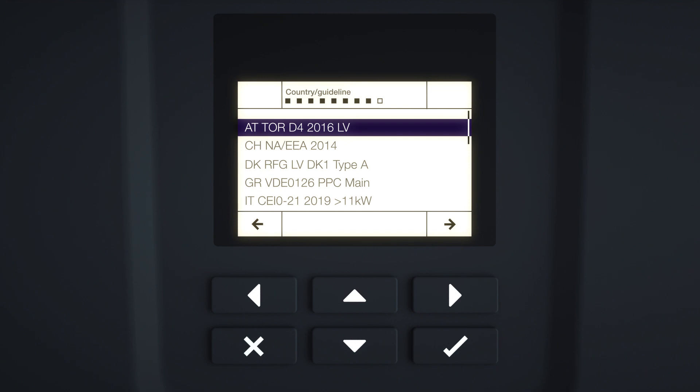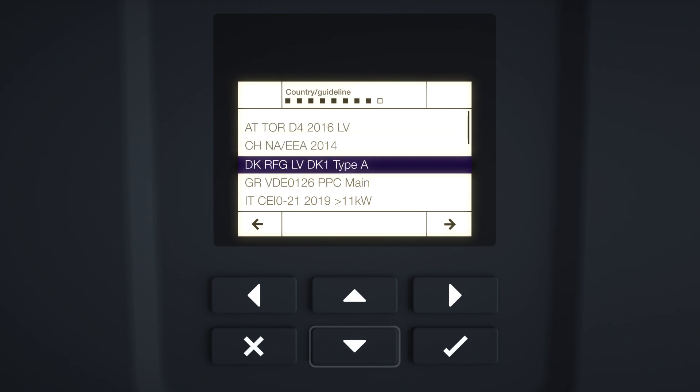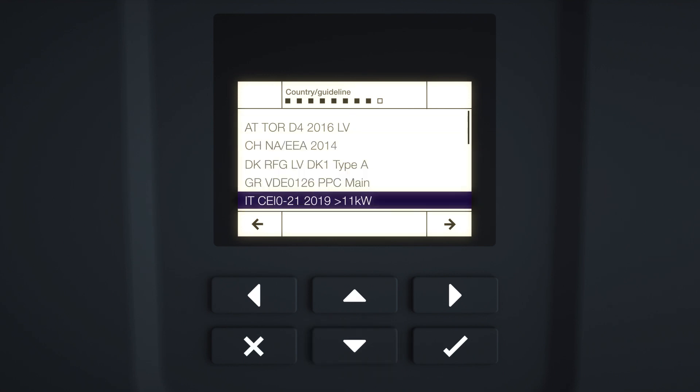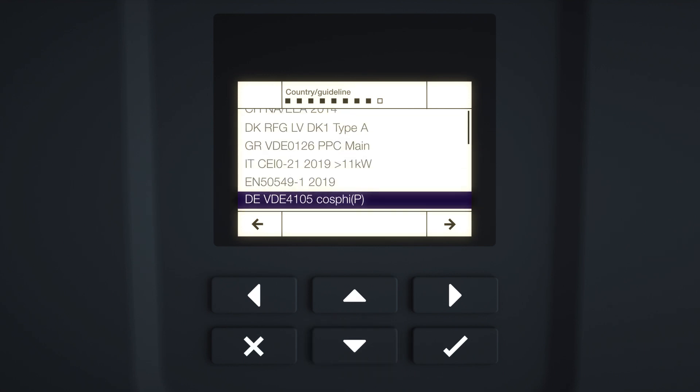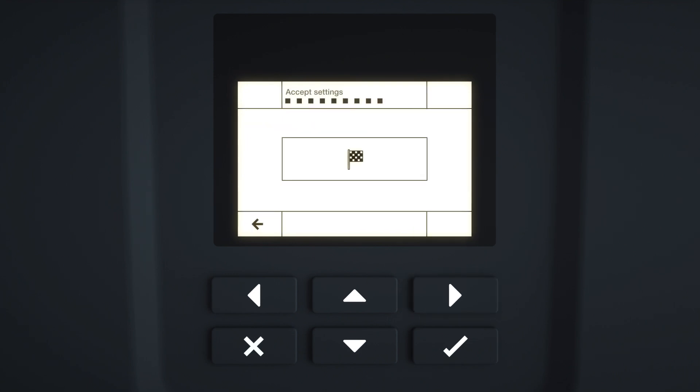The Country Guideline menu appears in the display. Ask your grid operator which guideline you need to set. Select the country or required guideline and confirm the input with Enter. Press the right arrow key to go to the next installation item.